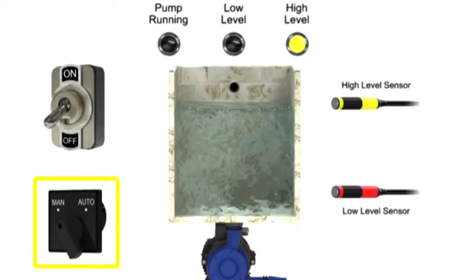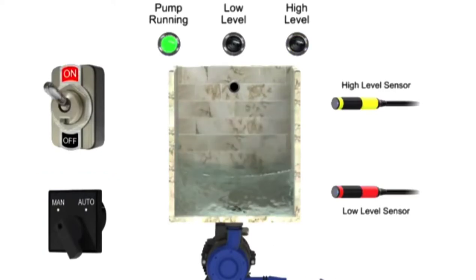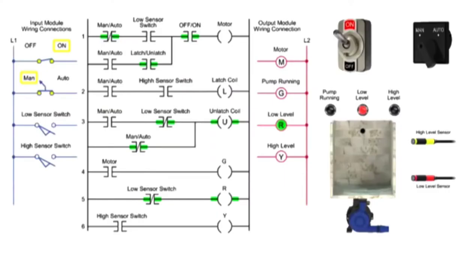In Manual mode, the program controls the water level by monitoring the low-sensor switch input. In this mode, the pump motor turns off when the low-sensor switch is off and turns on when the low-sensor switch turns on.